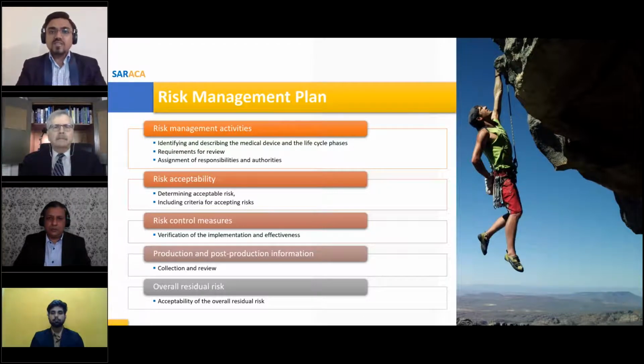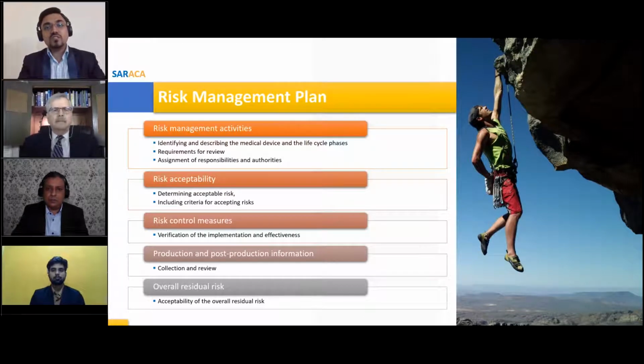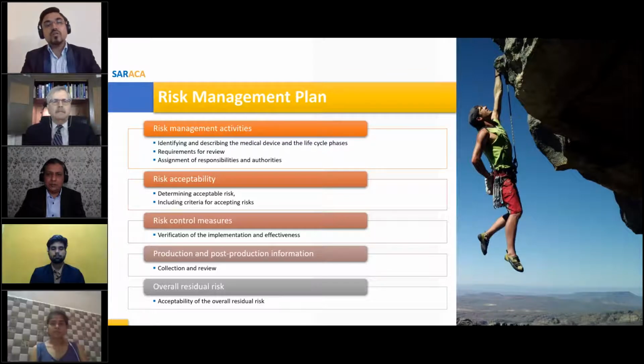How can you list down the requirements? Risk management activities: you need to identify and describe all the medical device and the life cycle phases. Your medical device life cycle and your medical device description you need to define in this section, and the requirements for review. What are the information, what are the requirements you need to review? Then you need to assign the responsibilities and authorities, that is, who is going to do what. You need to assign the responsibilities to all the authorities.